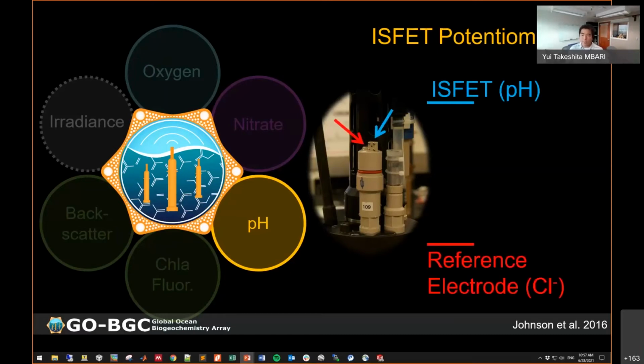The other electrode is a reference electrode, which is an ion selective electrode for chloride, shown in the red arrow here. It responds to chloride ions, or salinity. So you measure the voltage between these two electrodes, and then you calculate pH using the Nernst equation. Each sensor is individually calibrated for temperature and pressure, so that we can calibrate over temperature and pressure ranges.